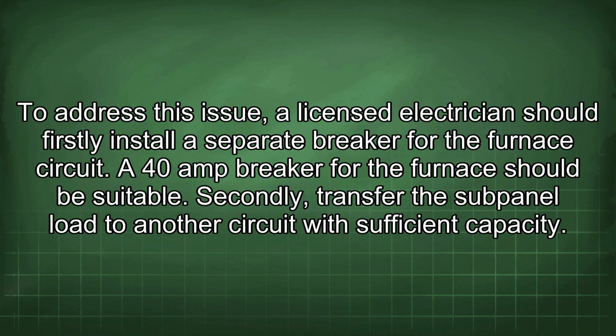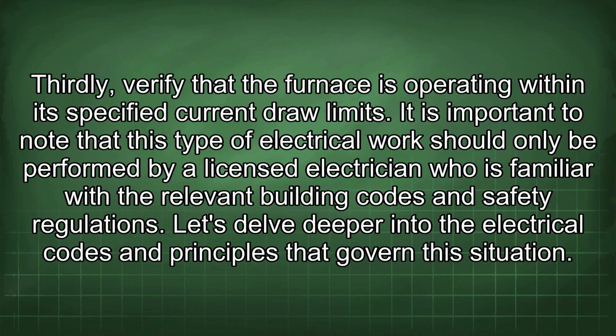To address this issue, a licensed electrician should firstly install a separate breaker for the furnace circuit. A 40 amp breaker for the furnace should be suitable. Secondly, transfer the subpanel load to another circuit with sufficient capacity. Thirdly, verify that the furnace is operating within its specified current draw limits. It is important to note that this type of electrical work should only be performed by a licensed electrician who is familiar with the relevant building codes and safety regulations.